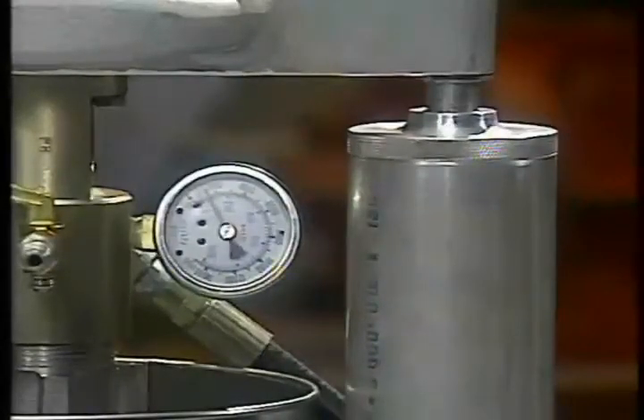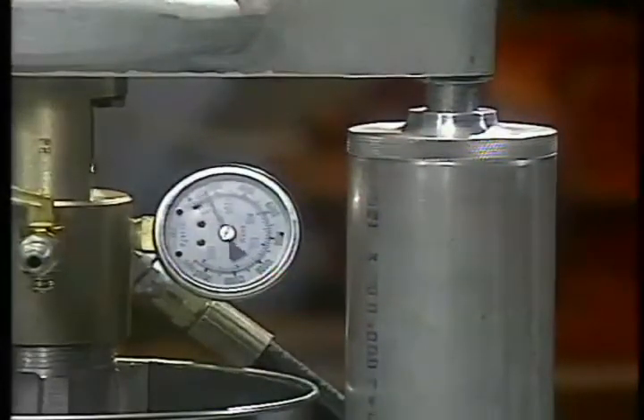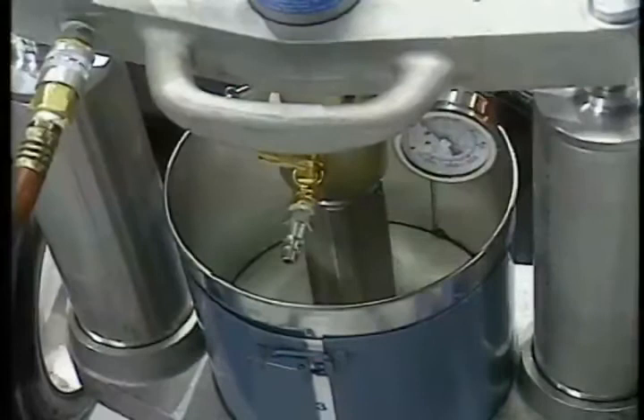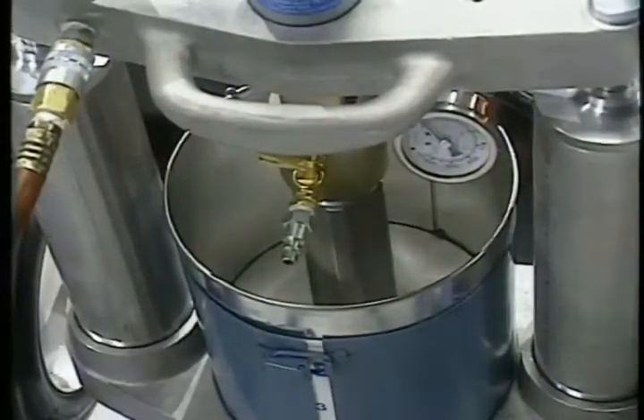At some point during the valve servicing process, the pressure reading on the gauge will begin to fall back to zero. The air motor will begin to pump faster, and the yoke will almost make contact with the cylinders. These conditions signal that all the sealant has been pumped from the 5-quart can. You need to stop operating the Hypregun and install a new can of sealant.